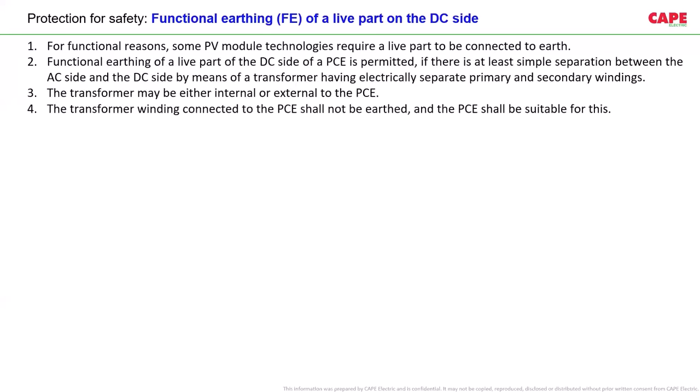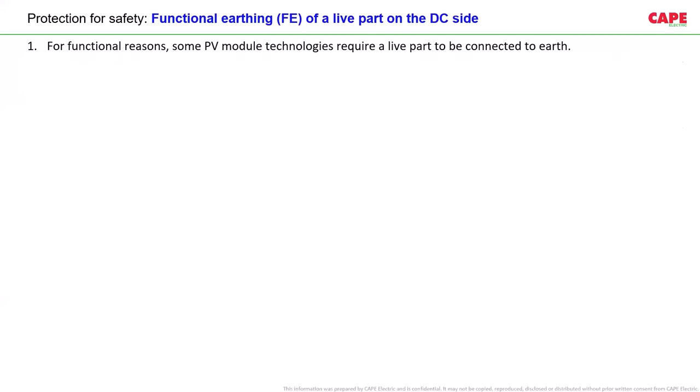If you use the functional earthing, you should also note down, for functional reasons, that some PV module technologies require a live part to be connected to earth. So not only the PV module, not only the inverter, the compatibility of the inverter and the PV module must be made in common.